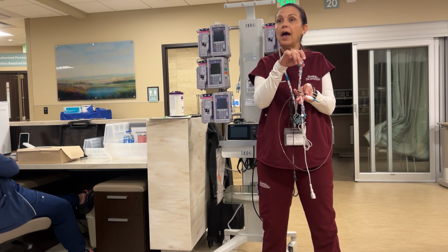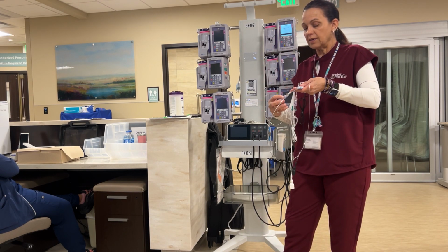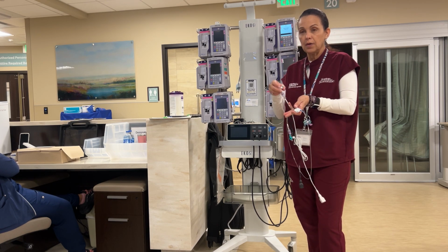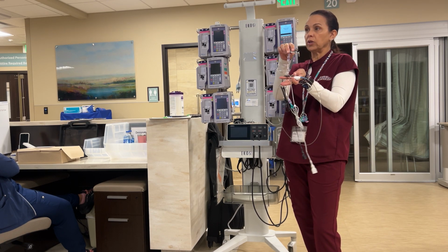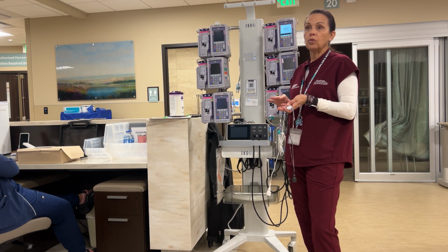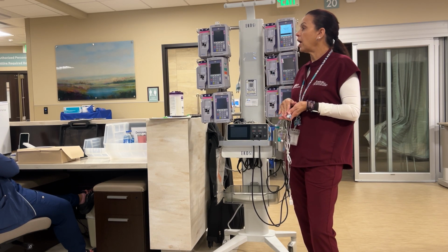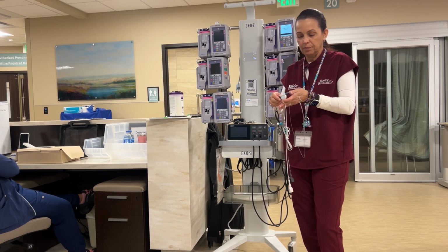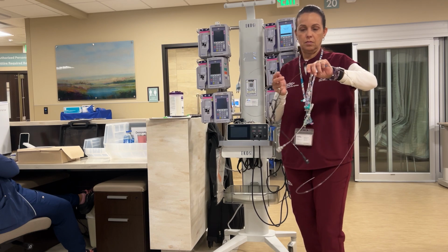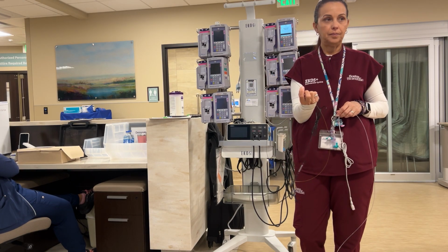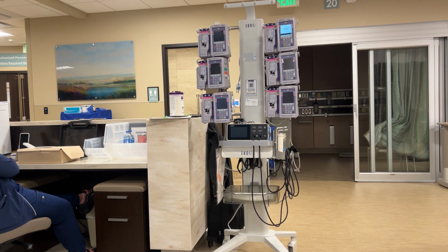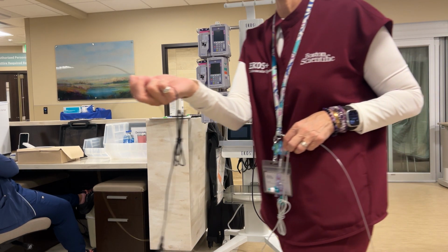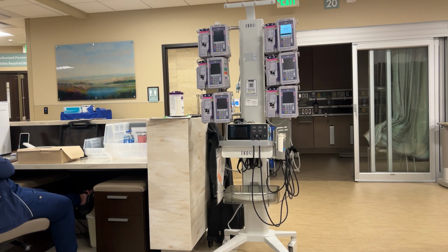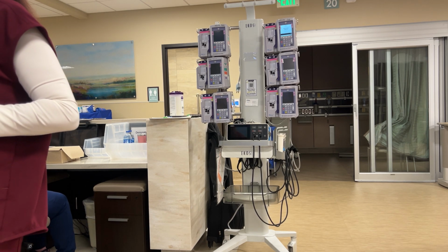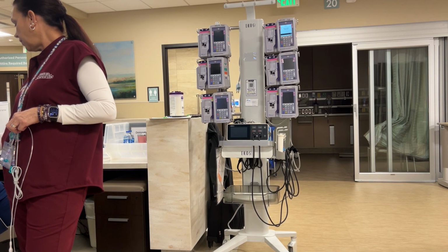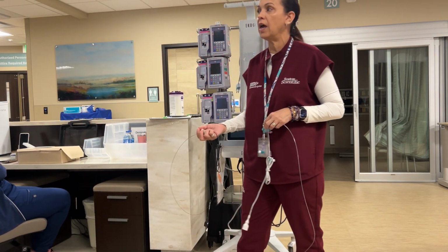Drug of choice is TPA, alteplase, used at a physician-specified dose, as mentioned, anywhere from 0.5 to 2 milligrams per hour. The other port, labeled and color-coded coolant, takes room temperature fluid, normal saline run at a minimum of 35 ml per hour, and can be titrated up to 120 as mentioned before. That is used to cool the ultrasonic core. Now the transducers, even as small as they are, about the size of a grain of rice, there's some heat that comes off the catheter. The room temperature fluid combined with the patient's own body fluid, their blood circulating around the catheter, is enough to keep the catheters cool and working efficiently.